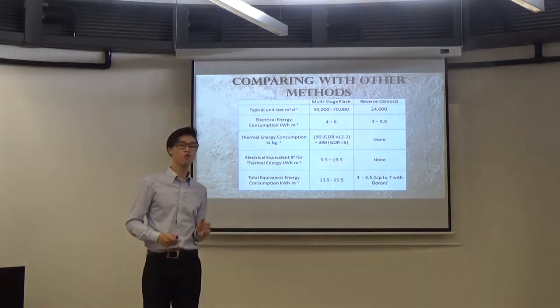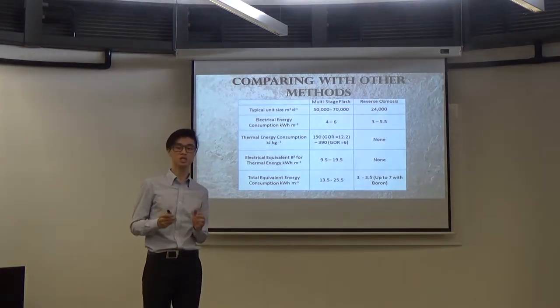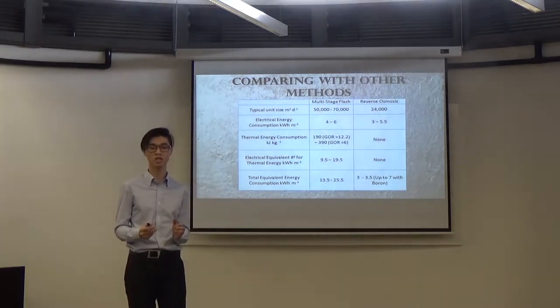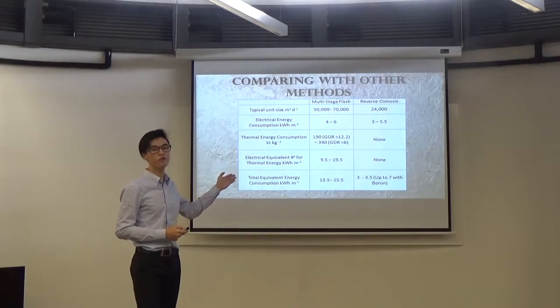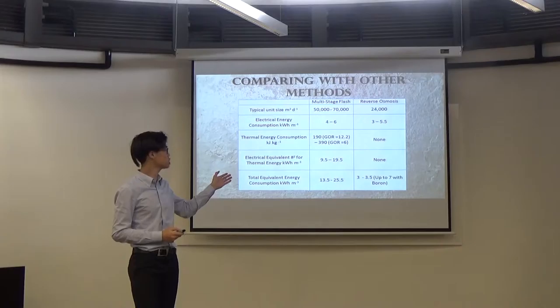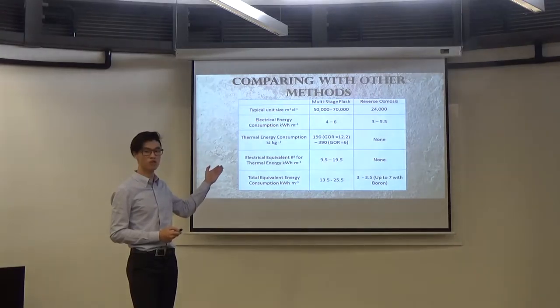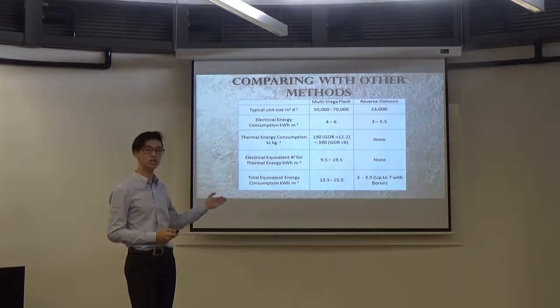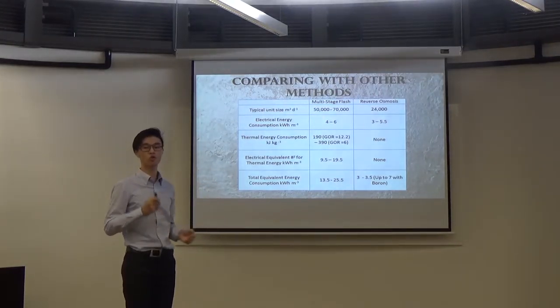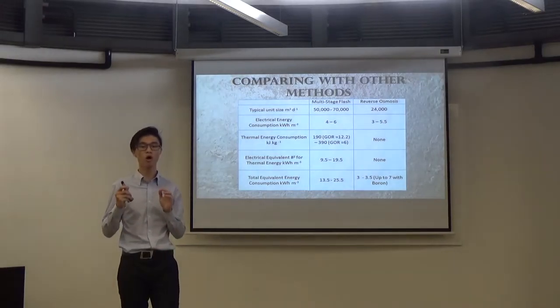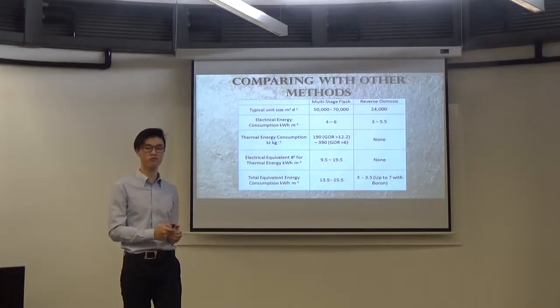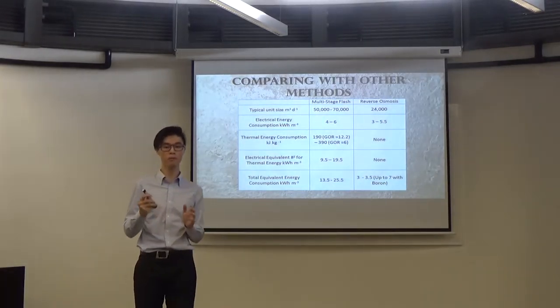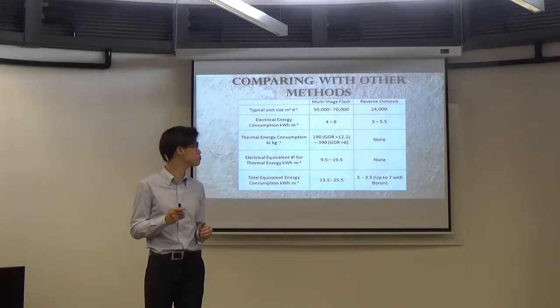With that being said, reverse osmosis is considered one of the most efficient methods for desalination today. This is in comparison with conventional methods such as multi-stage flash distillation which uses 13.5–25.5 kilowatt hours per meter cube, as compared to 3–3.5 kilowatt hours per meter cube for reverse osmosis.